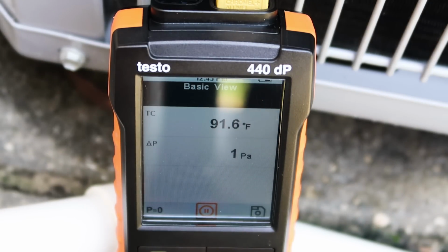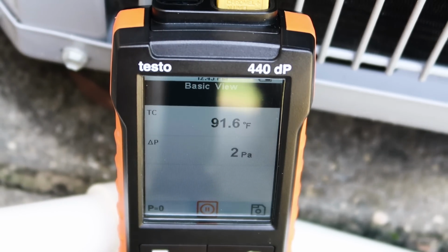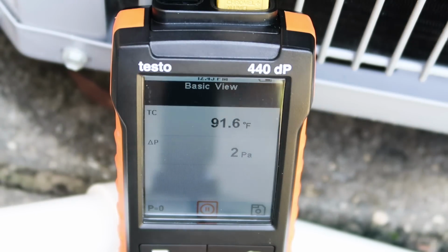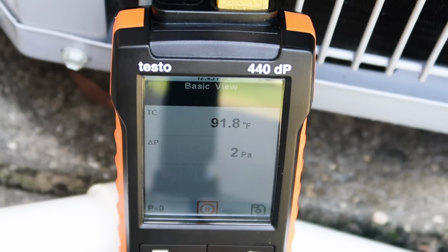Interesting, kind of an unintended consequence happened here. That compressor is running backwards by the sounds of it. Yeah, we've got a backwards running compressor now. So I'm going to let it reset enough that it can actually run properly, so I don't damage it.